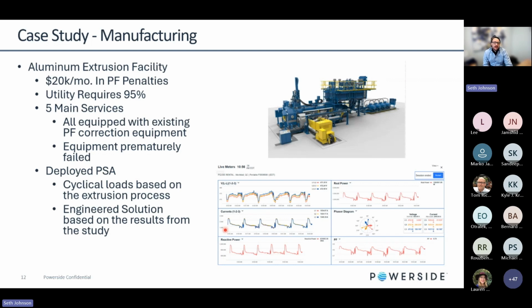So correcting for power factor, in this case, we wanted to look at being able to do more instantaneous power factor correction, so that we weren't just using typical contactor switches. One of the reasons we figured out that the equipment on site had failed is because it wasn't designed properly to dynamically respond to this type of load profile. Again, this is an example of the QubeScan platform that we're using in real time while connecting to the customer site, and we're looking at the load profile and the swings that we're seeing in current, reactive power, harmonics, voltage, etc.